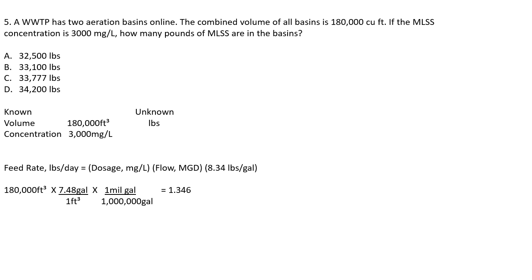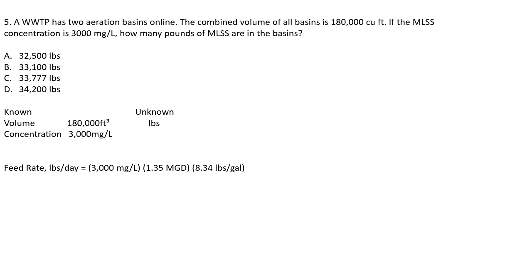Plugging into the pounds formula: 3,000 mg/L times 1.35 million gallons times 8.34 lb/gal = 33,777 pounds of MLSS. Answer: C) 33,777 pounds. That's it — five quiz questions solved. Hopefully this helps you learn. Thanks.